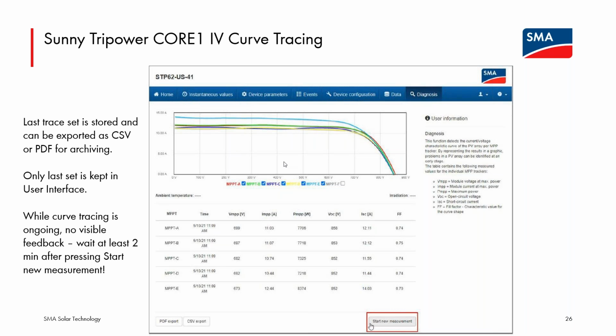So in the user interface of the inverter, and this is what we're showing, we've logged into that self-hosted user interface. You can trigger a new measurement. It will do the IV curve traces. So give it about 2 minutes. I don't believe you'll see anything like a countdown timer on the screen. So just give it its time to run. And when it's finished, the new curves will appear in this screen.